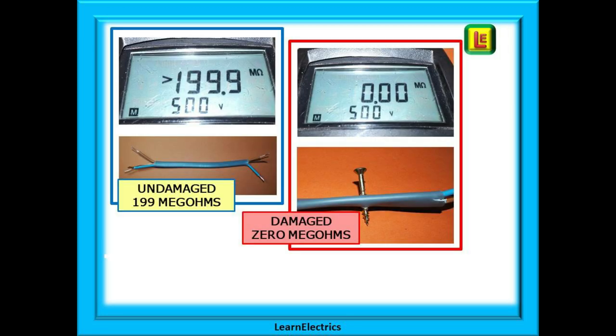Here are two images of meter readings. On the left, the cable is undamaged and the meter maximum — 199 megaohms in this case — is shown. On the right, it is obvious that the cable is damaged. The screw has penetrated the insulation and now the phase wire has a direct short to the earth conductor. A reading of 0 ohms is shown — a direct short.